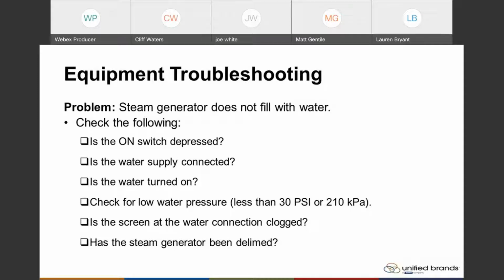And now for all the technical guys out there, yes, this is flow and not static. For the non-technical, they're going, what does he mean, flow versus static? There's a way to look at your pressure gauge, and once you're turning it on, it's still under pressure. You're going to see that the gauge is sitting there, which we register as static. Once you turn the unit on, water starts to flow. You're going to get that flow then on that gauge. The gauge has to maintain a minimum of 30 to 60 PSI, all right, to make certain that the unit operates properly, functioning properly through all the particular sequence of events that happen with the unit.